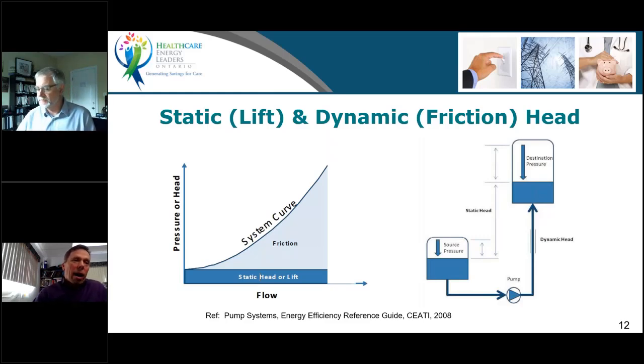Some clients had a high-rise building and did not know about open systems and static lift, and they thought the pump needed to work more because it was going 20 stories high. But what they did not get is that it's coming down 20 stories and pushing the water back up. So I always tell people, if you've got a pump here and the top of the loop is here and you're running it around, whether you run it this way or this way, it doesn't matter. It's the same friction in the pipe, which is all you're looking at, what's called the friction head, and basically what goes up comes down. So there's no difference in what the pump will experience in those situations, as long as the system is closed. If the system's open, completely different story.